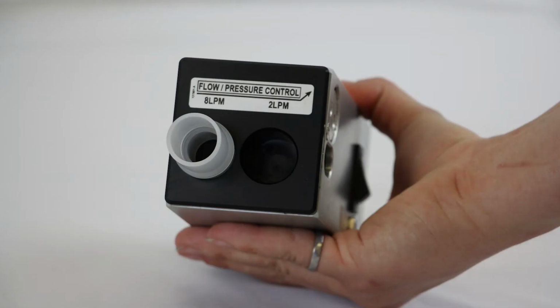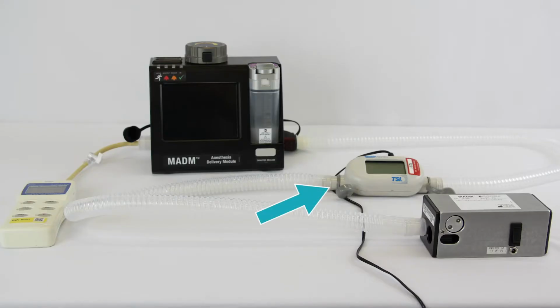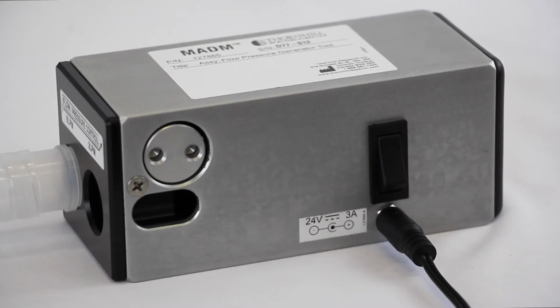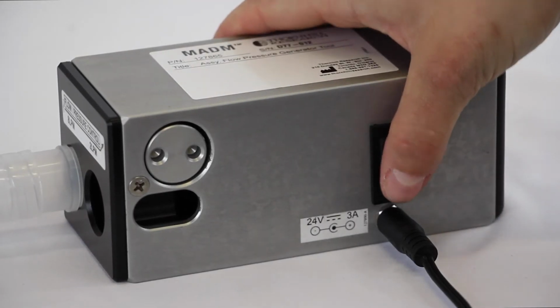To set up for the pressure leak test, connect a patient sensor circuit adapter to the 8 liter per minute port on the adjustable flow source. Connect one piece of patient tubing from the adjustable flow source to the flow meter, then connect a second piece of patient tubing from the flow meter to the inlet sensor on the right side of MADM. Connect the pressure leak test plug with tube to the MADM outlet port, then connect the pressure meter to the pressure leak test plug with tube. The MADM does not need to be powered on for the test.